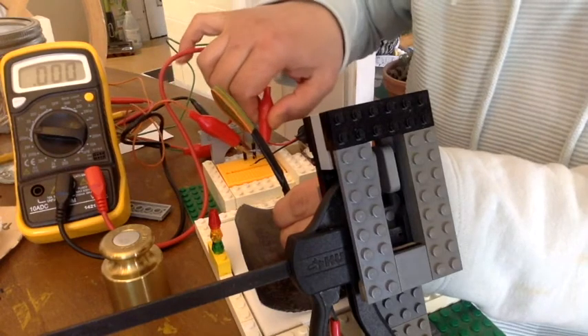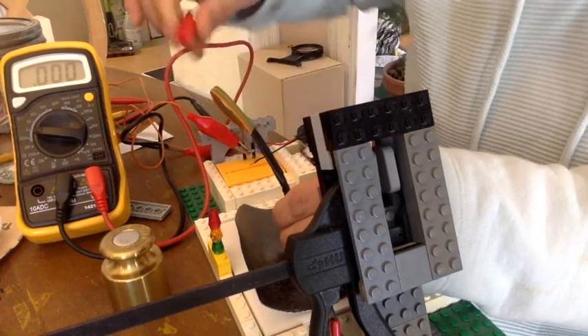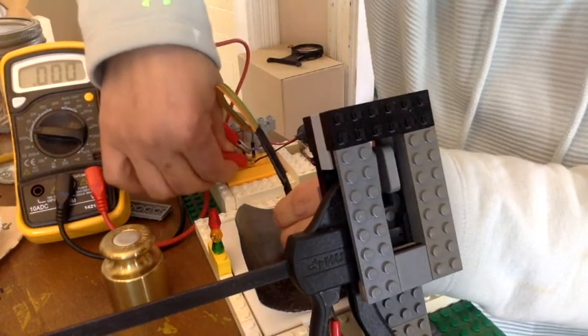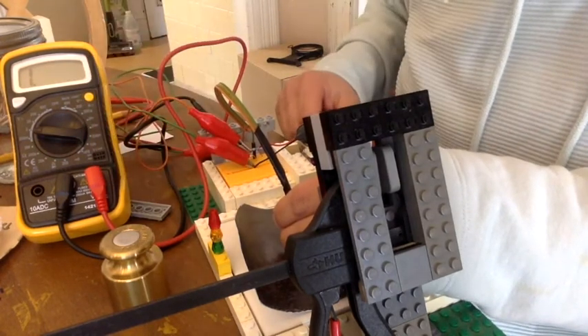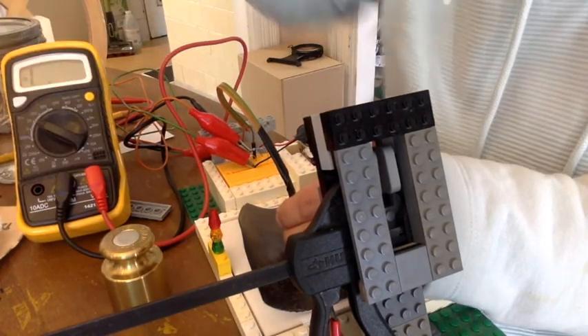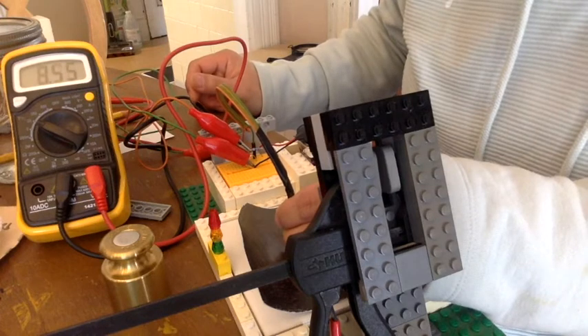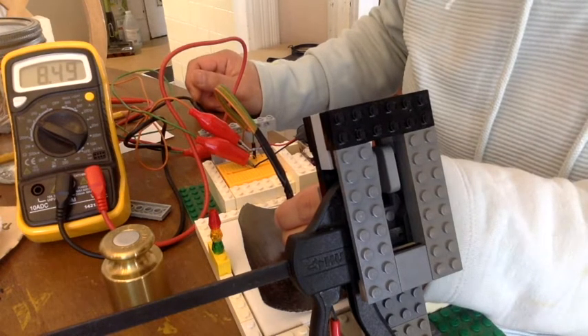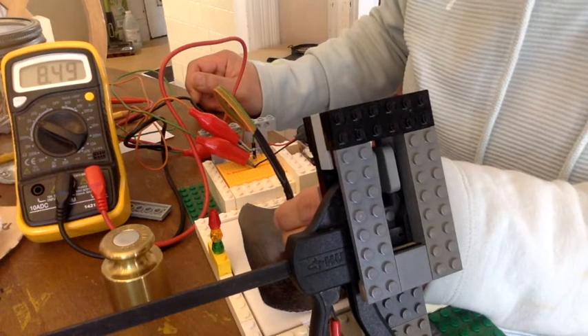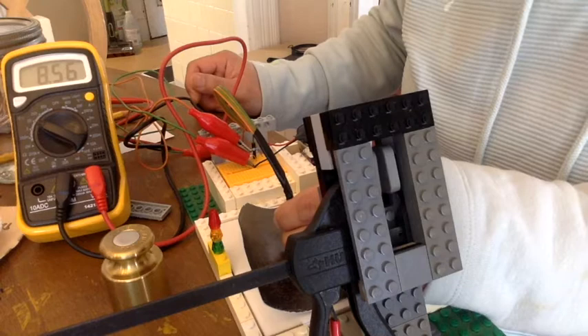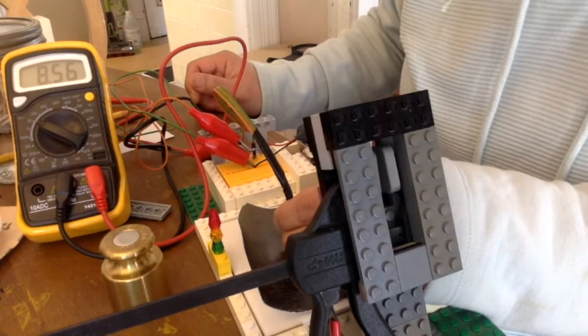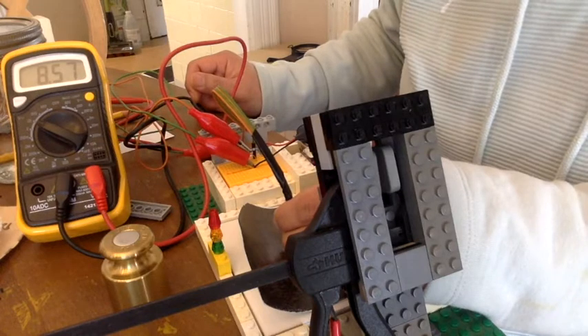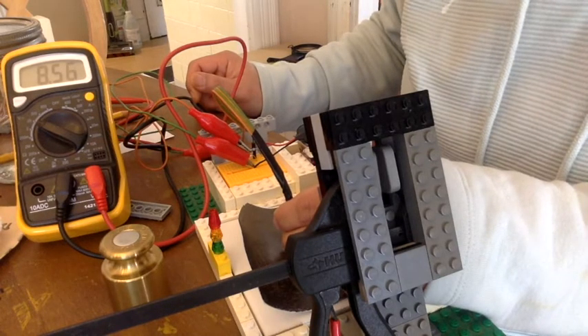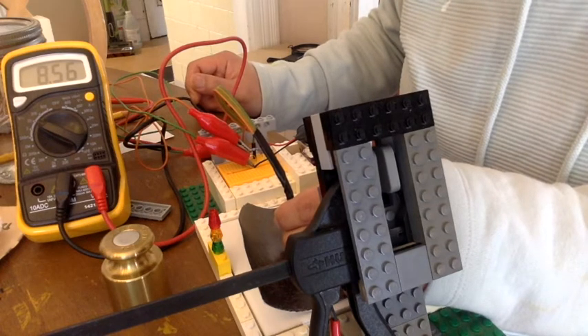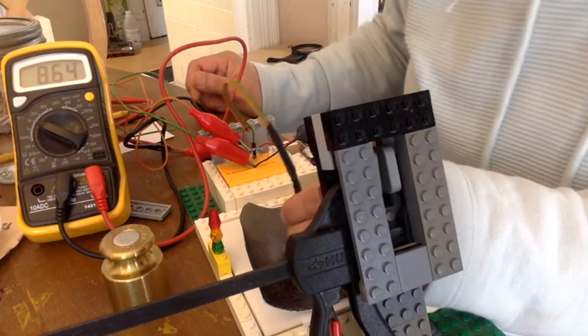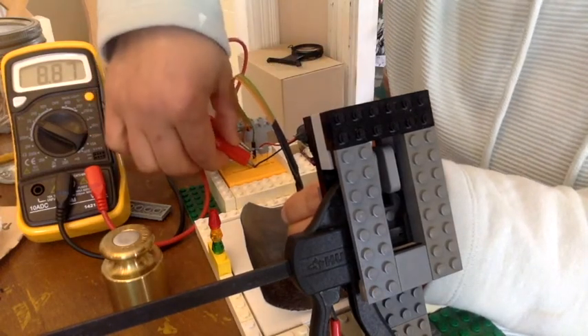And then I'm going to switch this over here to the other end of the battery, which will be testing the voltage between the two outer probe tips. So we should be getting a voltage drop there. So yep, we're getting about 8.49 volts across the outer tips. Oh, 8.56. And so you can see that this instrument is highly contact dependent. Getting the 4 probes into the right configuration is really important.